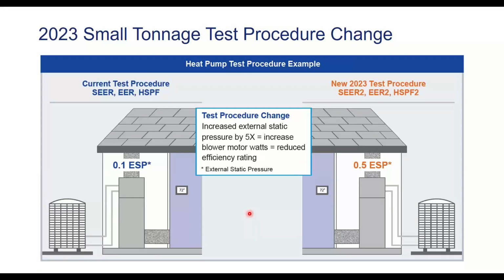Then to make it more complicated, not only do we have to go to these higher SEER ratings for this small tonnage stuff, but the way the small tonnage stuff gets tested for AC and heat pumps is also changing. So today, everything is tested at 0.1 external static pressure. That's almost nothing. That's almost zero airflow, right? It's not real. So the new standard will require it be tested at 0.5 external static pressure. That means something that was published at a certain energy rating now will have a much lower energy rating after it goes into the new test, because they're testing it with more static, which means more fan speed is required to overcome the static, which means that it's going to use more energy. It won't use more energy when you install it in the building, right? Because it's going to use whatever energy it needs to get down your crappy duct system. But as far as the test goes, it's going to look different on there.